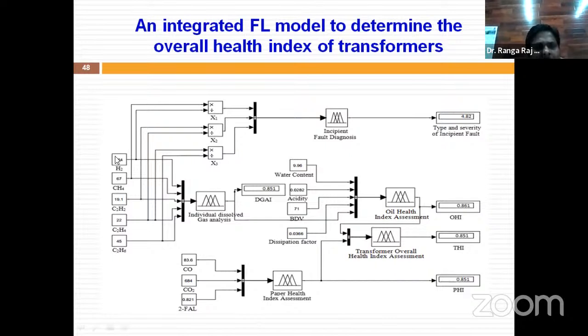Based on the oil gases and their quantities, we determined the DGA based index. In addition to this analysis, I considered some other tests related to oil, such as water content, acidity, BDV, and dissipation factor. Deciding the output based only on oil gas concentrations is not reliable. So along with the most important test, I considered 4 to 5 other tests as well, and determined the overall oil health index.